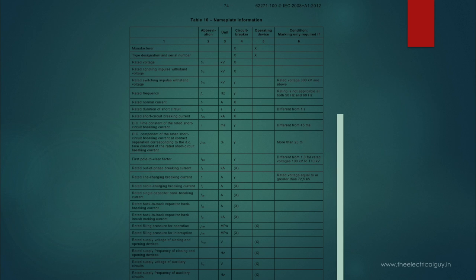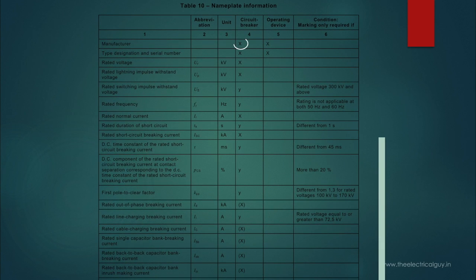As per IEC, these are the parameters which should be mentioned on the nameplate of a high voltage circuit breaker. Some of them are mandatory and some of them are optional based on specific conditions. Parameters marked with X are mandatory as per standard. All manufacturers producing circuit breakers based on this standard should mention all parameters marked with X on the nameplate.